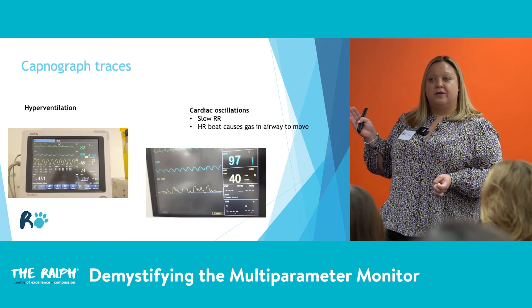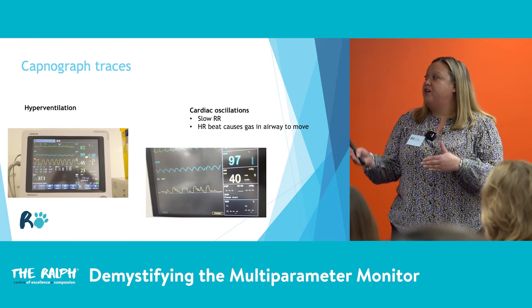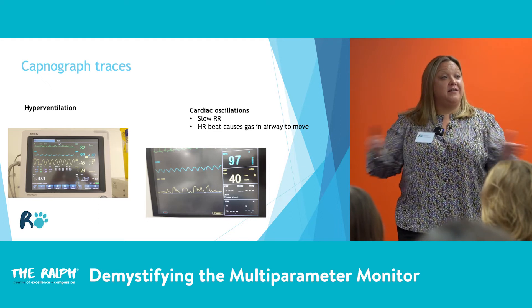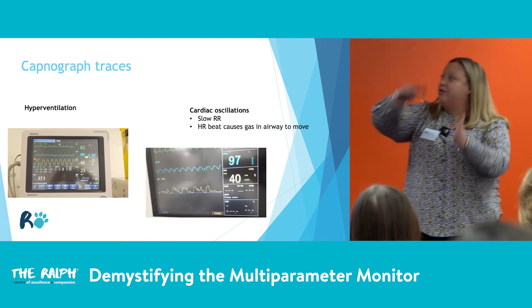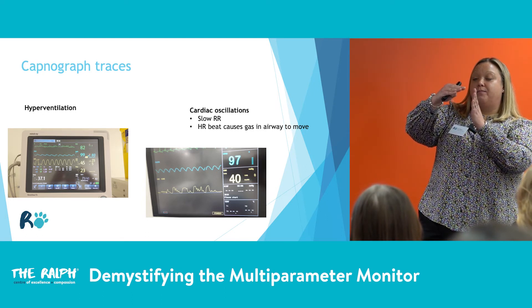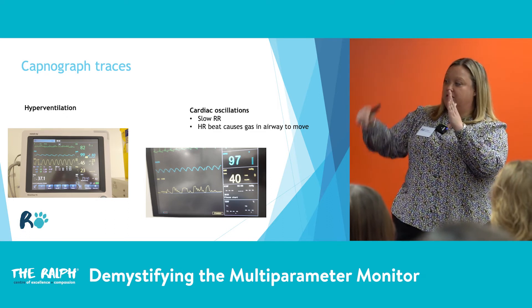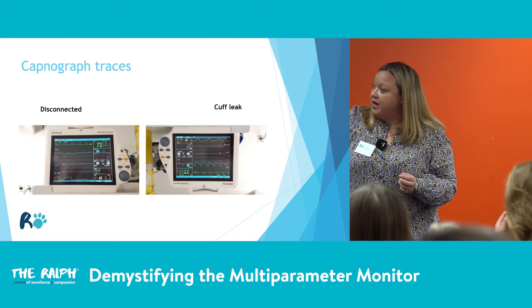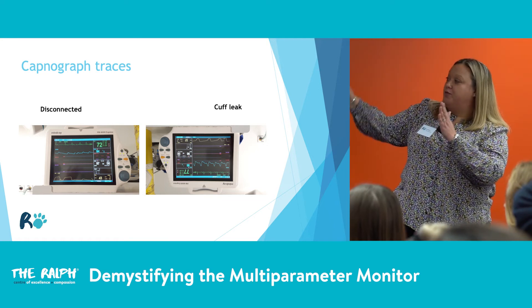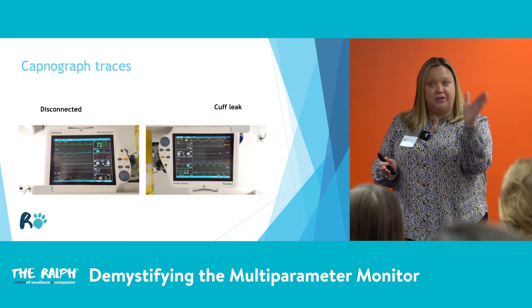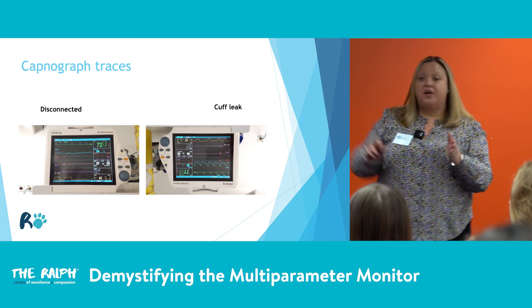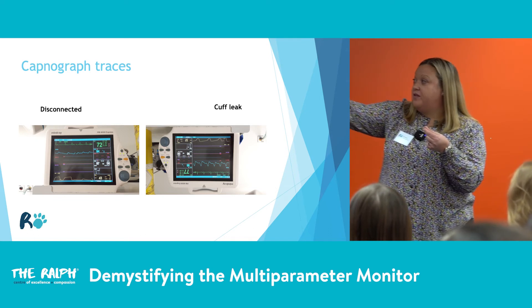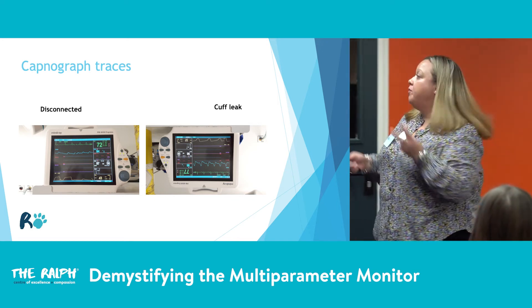Cardiac oscillations — have people heard of these? That's great. When I was in my previous job doing a lot of anaesthesia teaching, it was one that always really surprised people. Cardiac oscillations are where the heart is beating and gas is moving slightly in the tube, giving you little artefacts on the inspiratory phase. I've got an example of disconnection here too — you can see your first initial lovely trace and then it starts to drop off because of the delay. Cuff leak is another common one: if you put a little more air in the cuff or even squeeze it slightly, you'll sometimes see that little notch disappear, so you know you've got a cuff leak.